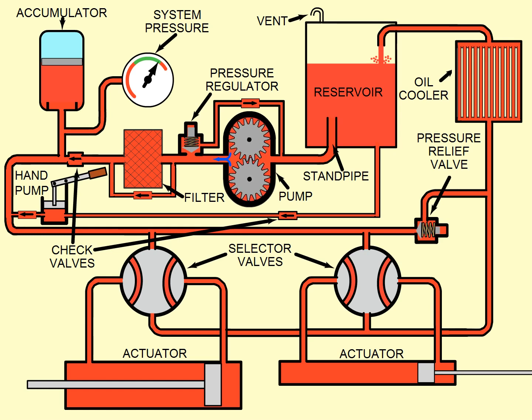If the actuator was operated slowly, or it was a small actuator, the additional fluid flow would be generated by closing the regulator valve slightly, with a minor movement of the accumulator piston to absorb the pressure surges as the selector valve opened and closed. As the system pressure is restored, the accumulator piston is forced back up to its normal running position, once again providing a reserve store of fluid for future use.